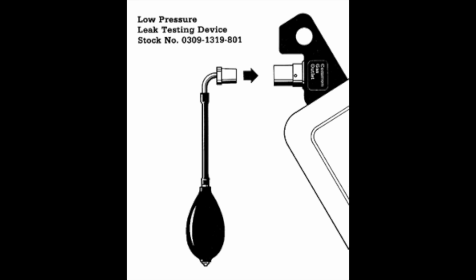To check for a leak, we'll need a suction bulb. If we don't have one, it can be easily prepared by taking the inflating bulb of a sphygmomanometer, reversing its valve, connecting a tubing to it, and connecting the distal end of the tube to a 15 mm connector of an endotracheal tube. Check the apparatus first by occluding the distal end and squeezing, and look if the bulb stays collapsed.